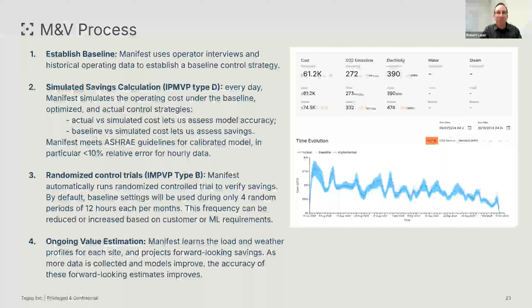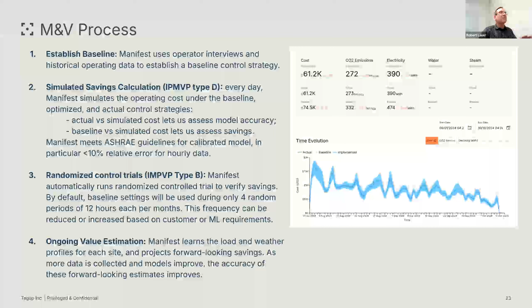There are ASHRAE guidelines about uncertainty levels for implementing control strategies, where you can compare the 5% to a rule of thumb of 10%, but that's just the relative error. The actual metrics we look at include CRPS metrics, which account for the width of the uncertainty bands, and a few other metrics generally used for machine learning models. The 5% is just one average error metric, calculated per implemented set point. If I switch to different scenarios and set points, I need to know the uncertainty of each. That's a threshold where we want to push all of these under 5% before considering implementation, but it doesn't quantify the uncertainty of the whole model, just one of the metrics.